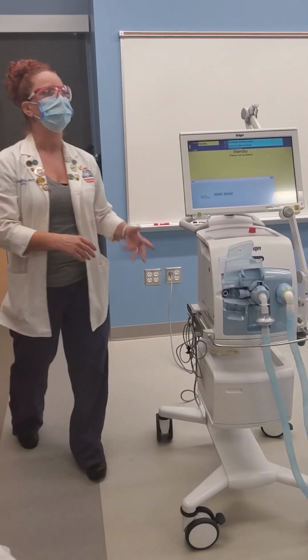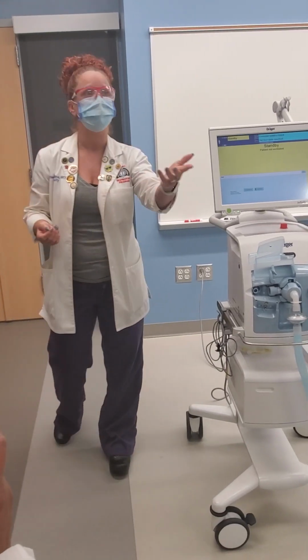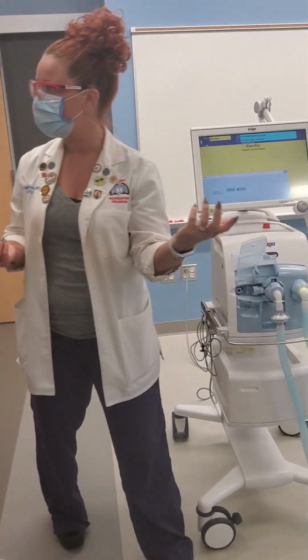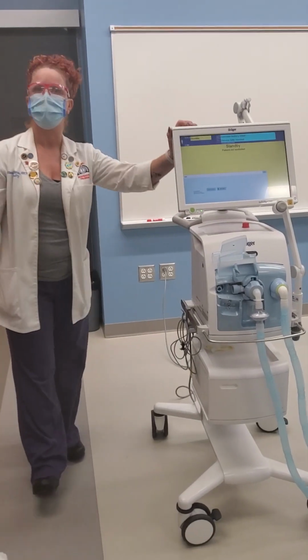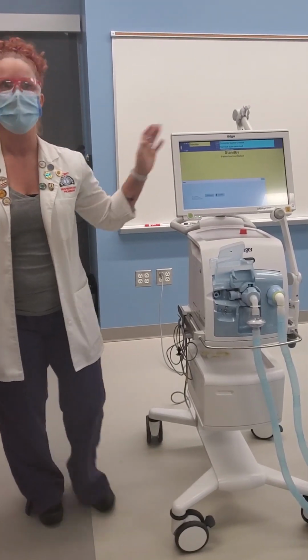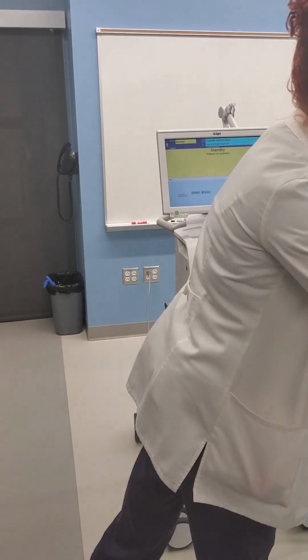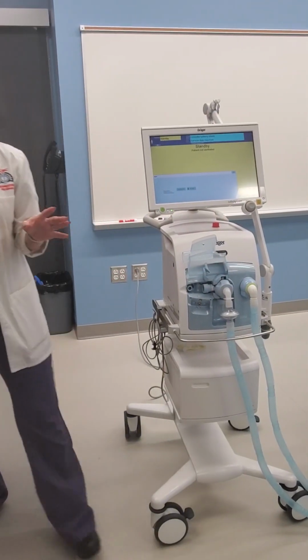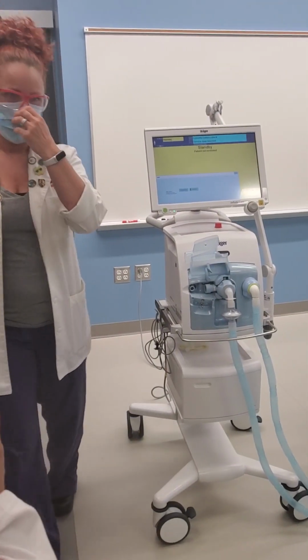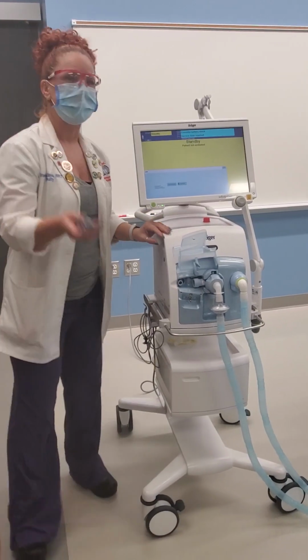However, if that doesn't work, try replacing the flow sensor with another one that's been cleaned. If that doesn't work, you may have to pull your ventilator from circulation, send it down to biomedical engineering, thank you, and figure out and be like, now it's your problem. No. Bag it, tag it, now it's your problem.